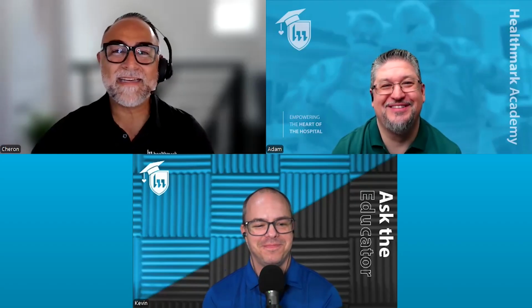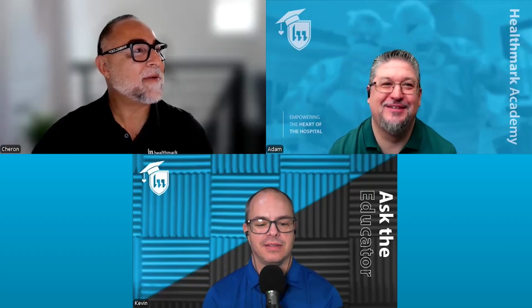Of course. So with the shaver study, which I know there's another one, I know Kevin's working on one. Yep, I can't wait to hear his. But mine, I know his is probably worse than mine, but it was a 92% failure rate, and that was 26 shavers, 24 out of the 26. And you're looking at a year-long study, 10 states, 28 hospitals, 92%. That's huge. And that was just the inside. When I looked at the outside, it was a 77% fail rate. That was 13 shavers, 10 of which had some type of integrity issue that was obvious. That was almost 80%.